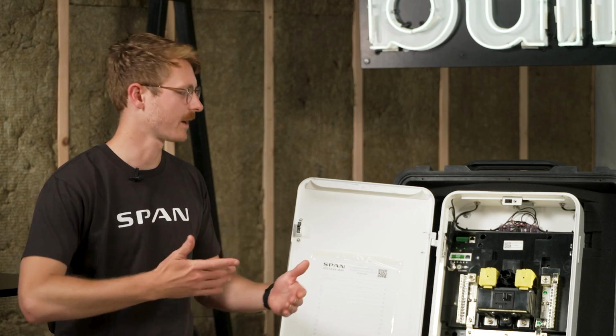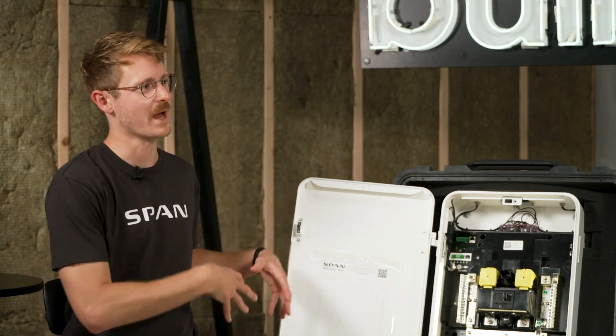For generators, the span panel can be installed downstream of an automatic transfer switch or a manual transfer switch, which you'd need anyway. So ATS first, then the span panel as the load center. We've been on projects with propane or natural gas generators and Tesla Powerwalls that play together, so if your batteries run out, you can still go. In those scenarios we follow the lead of the battery system, and they manage the generator, so it looks a lot like the existing battery experience.